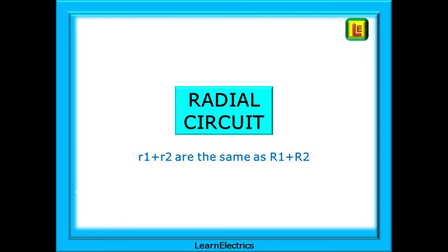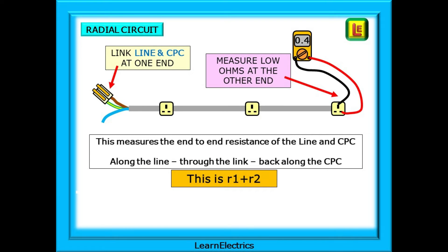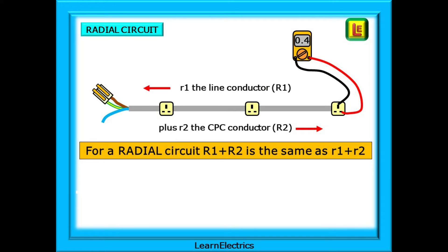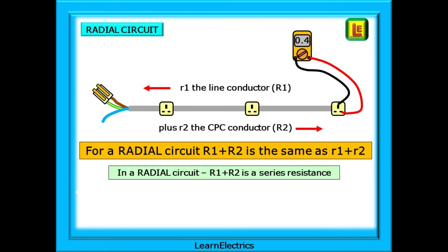Let's begin with a radial circuit, where we will find that little r1 and little r2 are the same as big R1 plus big R2. To find big R1 plus R2, we link the line and CPC at the consumer unit and measure for low ohms at the furthest point. This measures the end-to-end resistances of the line conductor, through the link and back along the CPC conductor, giving us little r1 plus little r2. As this is a radial circuit, big R1 plus R2 is the same as little r1 plus r2 — the effective resistance equals the actual resistance. R1 plus r2 is a series resistance.